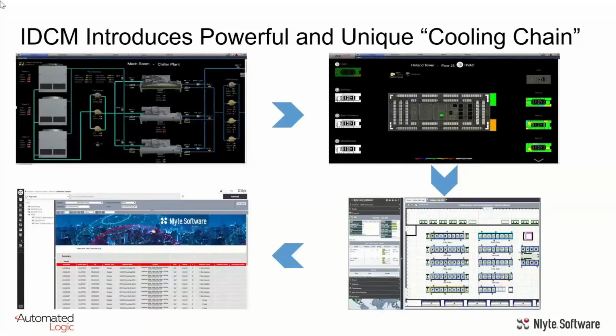Here we'd like to introduce the unique concept of a cooling chain, much like you have a power chain. Let's say there's a maintenance event, and one of the chillers in the chiller plant is going under maintenance. That information is relayed through WebCtrl to the facilities manager, who is then able to isolate the chilled water produced by that chiller, isolating the part of the data center affected by the lack of production from that chiller. This is then mapped onto the floor of the data center, and the information is sent to Nlyte, which will take the necessary steps to create the necessary workflows.